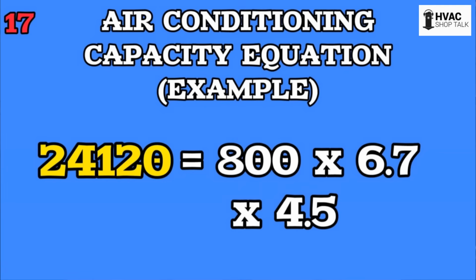Now, in the real world, there'll be issues with the system: bad ductwork, bad charge, blocked airflow, all sorts of stuff. So the airflow may be lower, and the enthalpy split may be lower if the system is low in charge. They may vary quite a bit. You'll get a certain amount of sensible and latent that add up to this number. So this is the total number, 24,000. You add those together, and that gives you the total.